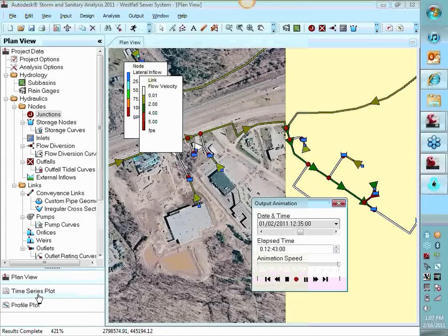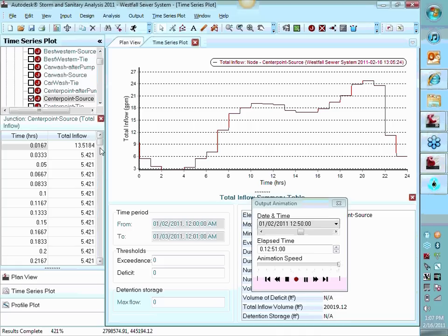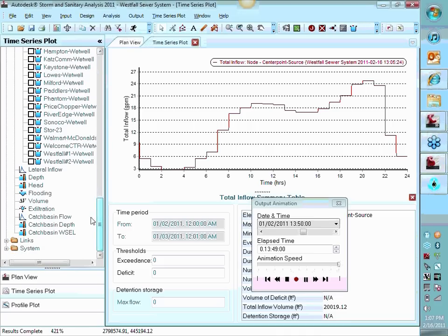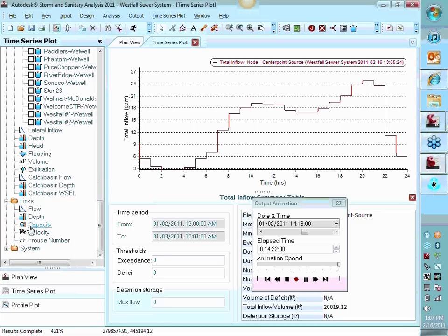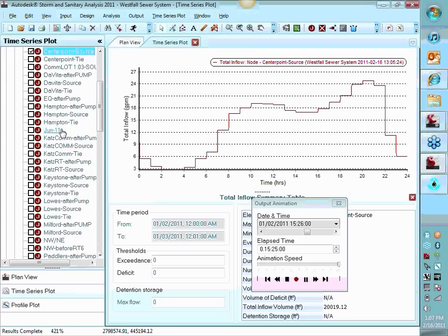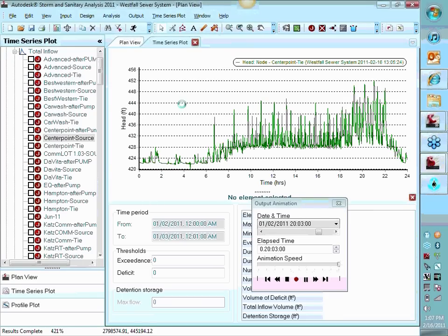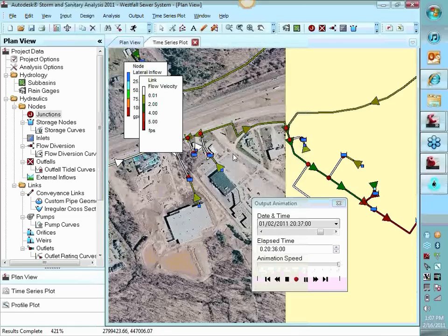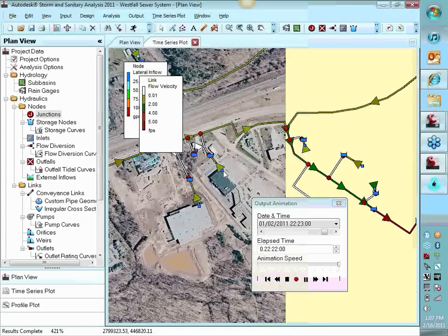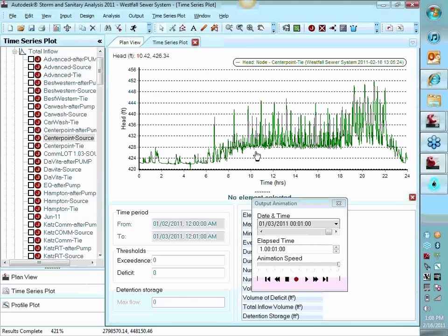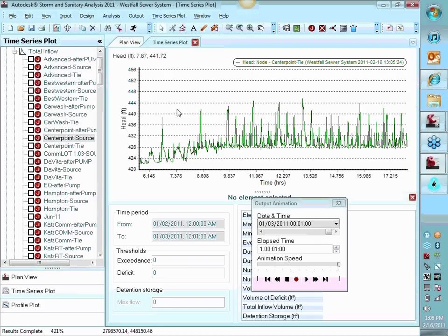And then you can go in your time series plots. And you can see if I look at links and I come down to head loss. So this is the head on the pipe. So that's the total dynamic head. That has to deal with elevation and all the pressure in the system. And that's right at this point, right here, where this shopping center pumps in. You can see how that head value, as you go into your eight o'clock, 10 o'clock hour, because there's so many pumps turning on at the same time, that head starts to increase.